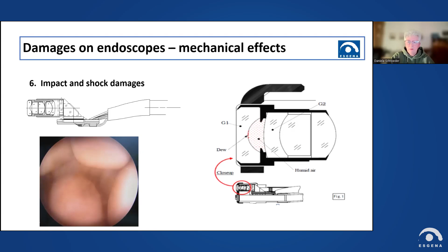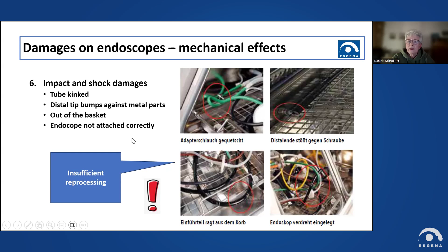Another point with shock damages, we all know the situation in the AER, especially with a bronchoscope. If there is no fixation, you will have some trouble in the AER, and this will also mean a bump against the metal parts of the basket, and then you will have another damage. Besides this, we will have insufficient drying if it's not really attached, or we have a kinked tube, or it's not attached correctly. All lesions, even if the endoscope can work properly, mean we have a micro lesion on the material, which is always a germ reservoir, and this is a high risk for patients to get an infection.